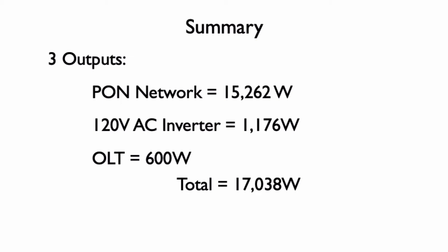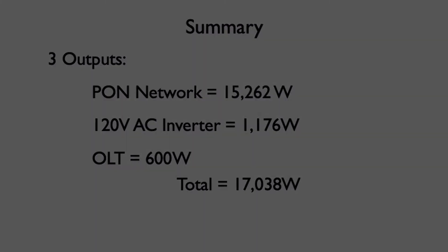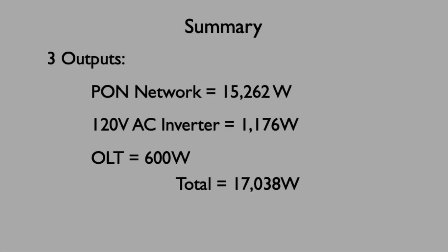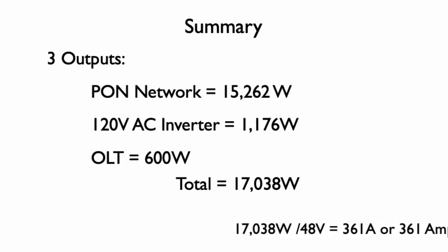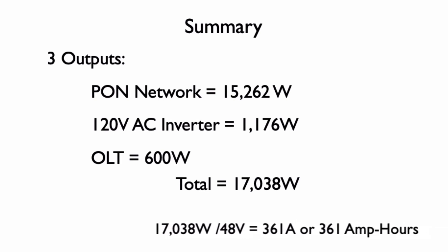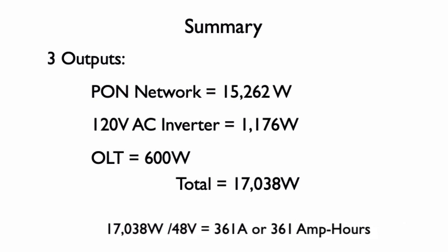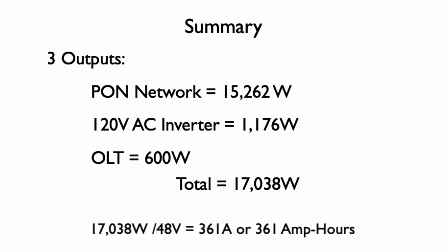Our customer wants everything to stay powered up for one full hour. Batteries are sized in current draw per time or amps per hour. At 48 volts the input current needed is 17,038 watts divided by 48 volts for 361 amps. So the battery needs to supply 361 amps for one hour at a one hour discharge rate or 361 amp hours.